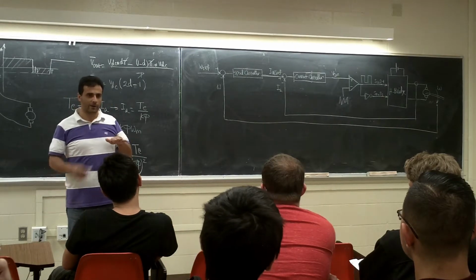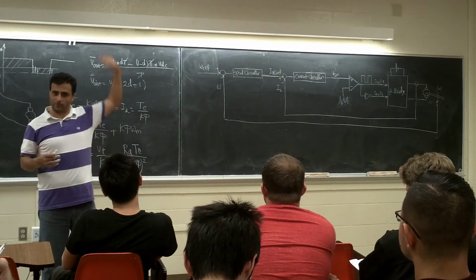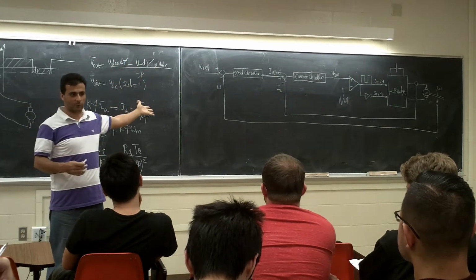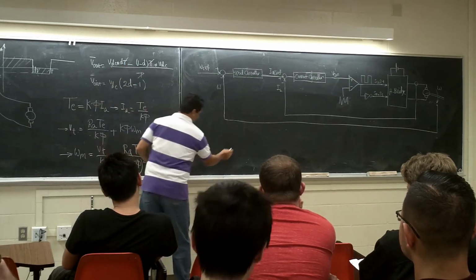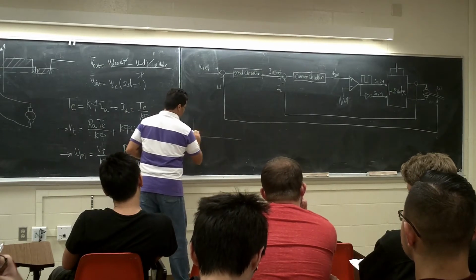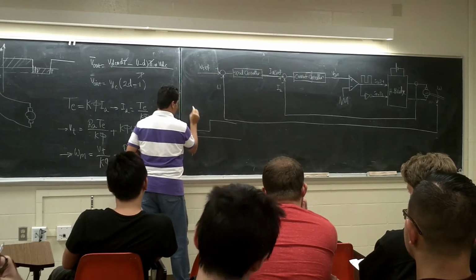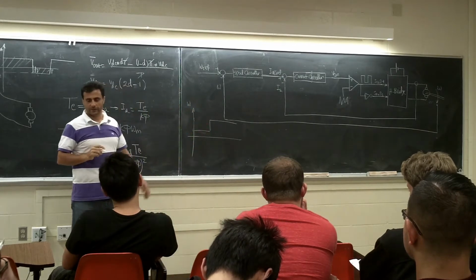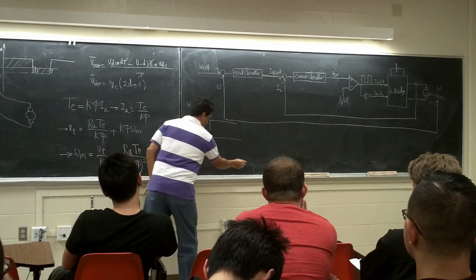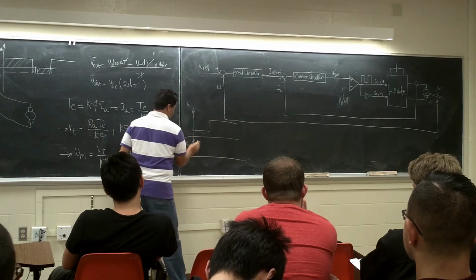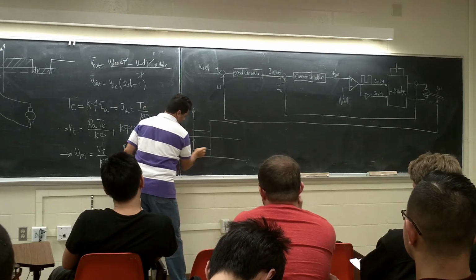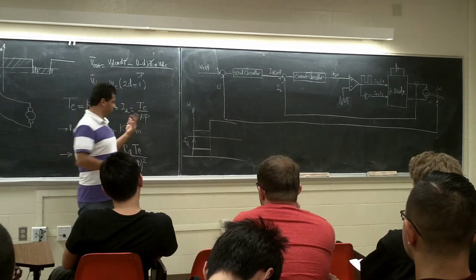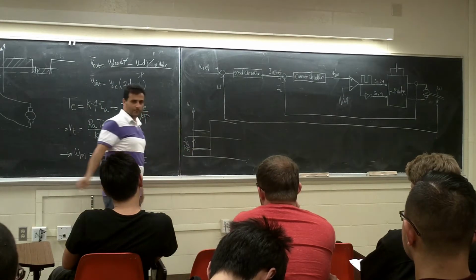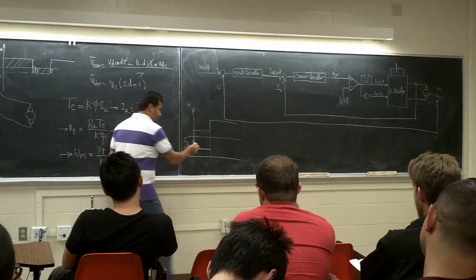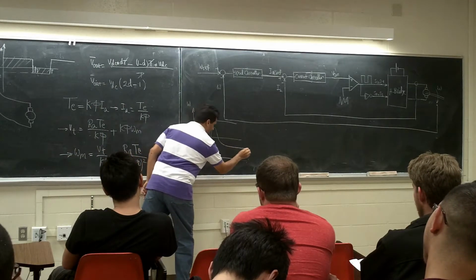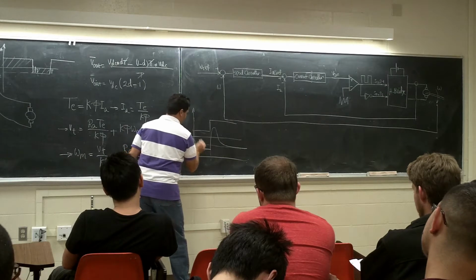At steady state the current cannot be very high because at the end you are not able to provide that. Let's say you want to go from this speed to this speed. If you don't have an internal current loop, IA is going to be like this. You are stable here, this is 10 amps for example. So what happens? It's going to go up and come back, and for this case you need 12 amps.